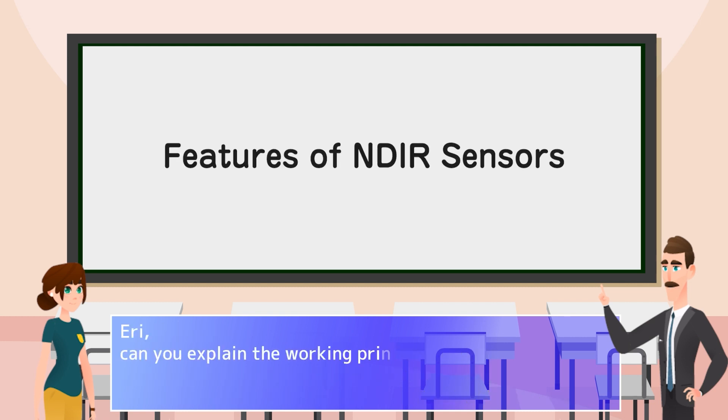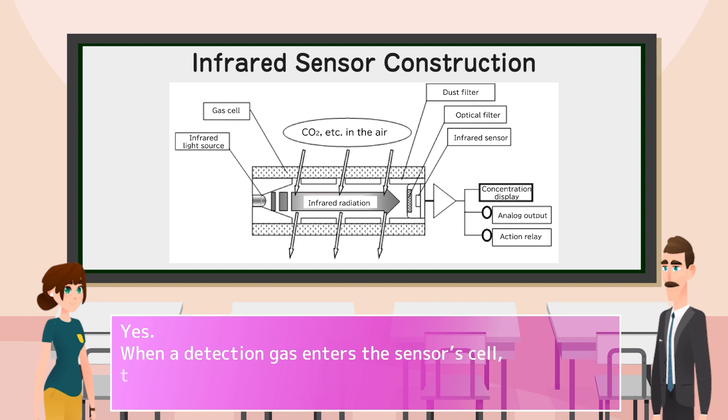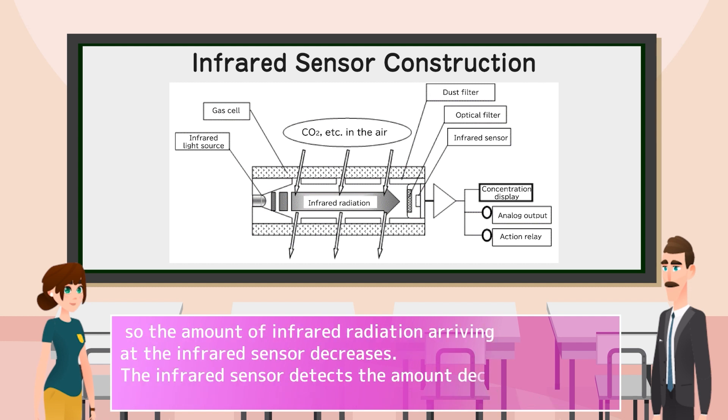Eri, can you explain the working principle of infrared sensors? Yes. When a detection gas enters the sensor's cell, the infrared radiation emitted by the light source is absorbed by the detection gas. So the amount of infrared radiation arriving at the infrared sensor decreases.